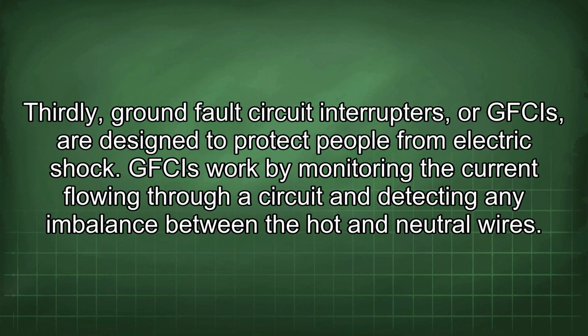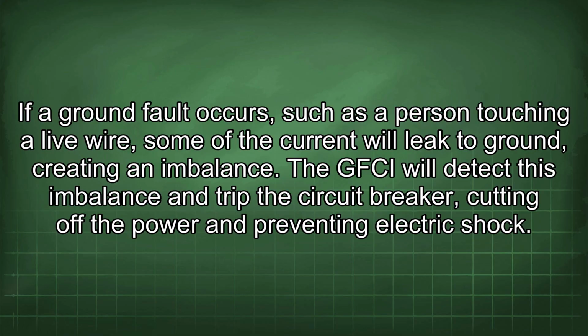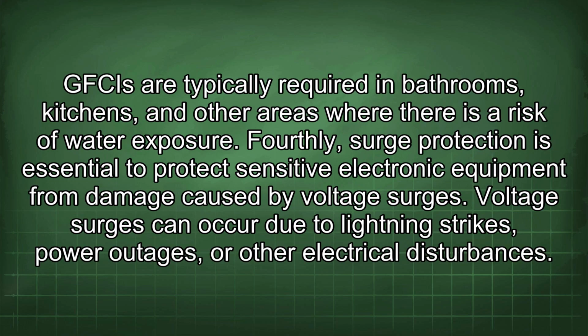Thirdly, ground fault circuit interrupters, or GFCIs, are designed to protect people from electric shock. GFCIs work by monitoring the current flowing through a circuit and detecting any imbalance between the hot and neutral wires. If a ground fault occurs, such as a person touching a live wire, some of the current will leak to ground, creating an imbalance. The GFCI will detect this imbalance and trip the circuit breaker, cutting off the power and preventing electric shock. GFCIs are typically required in bathrooms, kitchens, and other areas where there is a risk of water exposure.